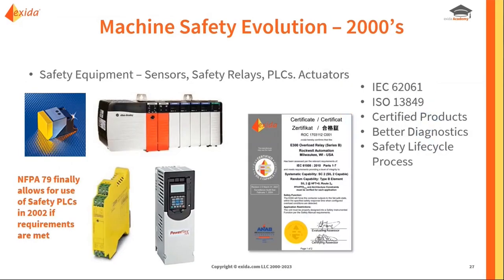In the 2000s, we're really starting to get more of our modern traditional machine safety certified equipment — certified sensors, safety relays, safety PLCs, actuators, safety contactors — that have been formally reviewed and certified. IEC 62061 and ISO 13849 come into use, we're getting better diagnostics, and we're seeing an overall safety lifecycle process. For the first time in 2002, NFPA 79 does allow for safety PLCs to be used if specific requirements are met. So we finally get into more of the modern day approach where safety PLCs are much more commonly used and adopted.